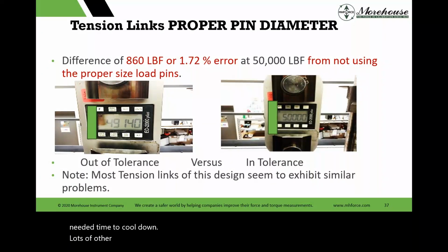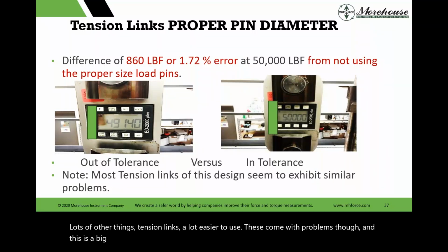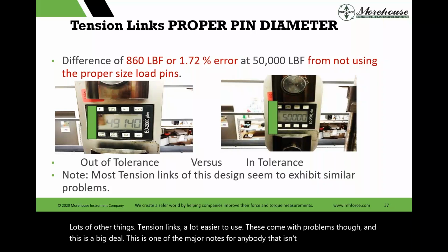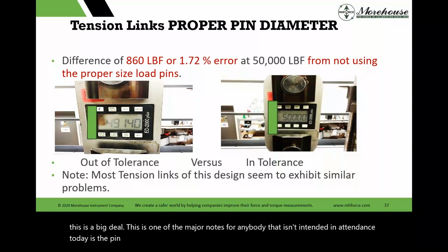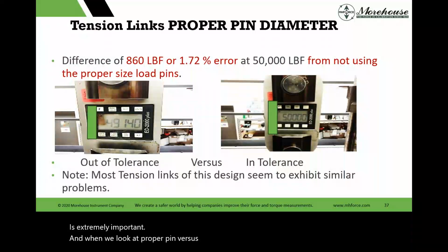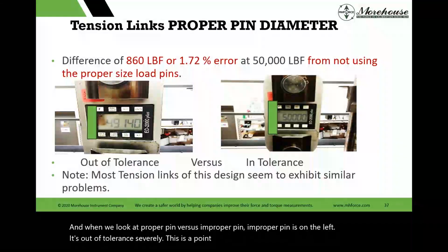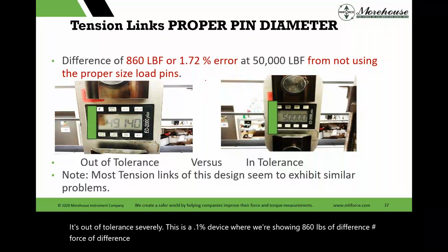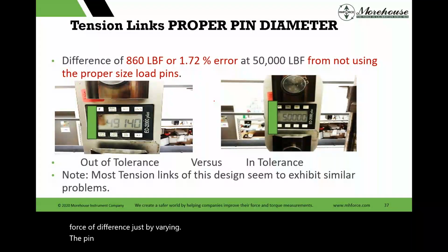Lots of other things. Tension links, a lot easier to use. These come with problems though, and this is a big deal. This is one of the major notes for anybody that is in attendance today: the pin size of what you put in to fixture the calibration of these devices is extremely important. When we look at proper pin versus improper pin, the improper one is on the left. It's out of tolerance severely. This is a 0.1% device where we're showing 860 pounds force of difference just by varying the pin size. And it gets worse.